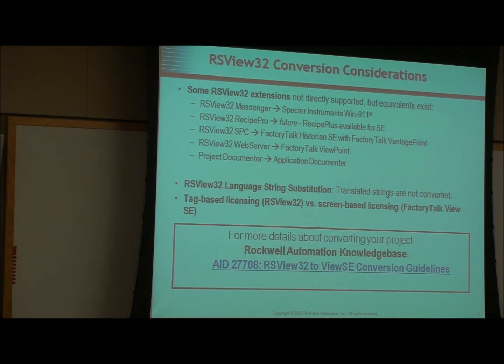If you're using 6.0 or 6.1, it's included right under Tools. You'll see Publish. Also, a note that I find so interesting is that you can have a separate main program for that web server than you do for the operator station. I found some OEMs and system integrators that have one set of navigation paths for the operators, but when they come in from the back end for diagnostics, they have a whole different set of screens that have no way to be reached from the operator, for use as diagnostics. Some have a set of screens for production supervisors, since the operators don't look at those, and they just want to see a couple of screens with production data. So the screens from the operator don't necessarily have to be the same ones you have out on the web browser.